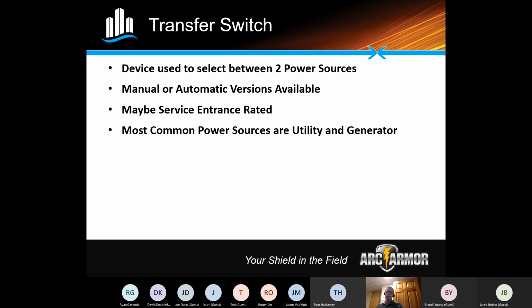Transfer switch: what is it really designed for? What types are out there? A transfer switch is really used to connect or select between two different power sources. That's pretty prevalent in lift station control panels. The transfer switch can come in a couple different flavors, manual or automatic. They may be service entrance rated. And again, they connect common power sources of utility and/or a generator.